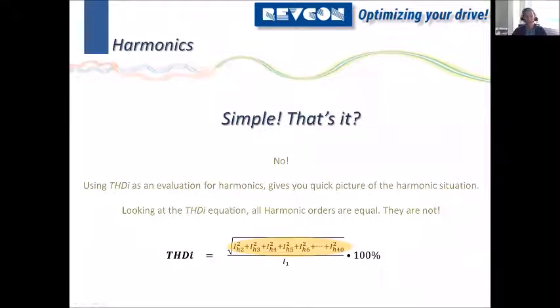Okay, so as I mentioned, it's not that simple. It's not only about the THDI. Using the THDI as an evaluation for harmonics can give you a first quick picture of the situation, but looking at the equation, this has one quite big problem. If we look at this right here, we can see all harmonics are equal. It doesn't matter if I have a high current on the 40th harmonic or on the second one. All these harmonics are equal, but they're not, because higher harmonics will cause more harm than lower order harmonics.